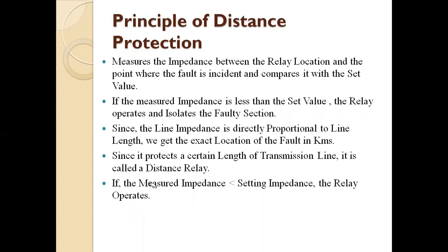In distance protection we are measuring the impedance. Impedance and admittance are important here, and your R, L, G and C components. We are measuring the impedance between the relay location and the point where the fault has occurred.